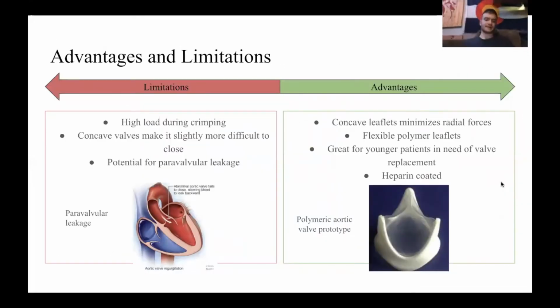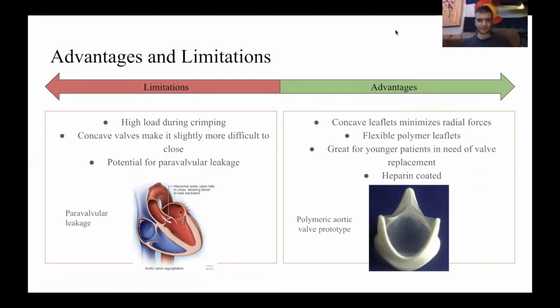So our device has advantages and limitations. To begin with the limitations, there's a high load during crimping. The concave valve shape makes it more difficult to close due to the blood pressure on the valve. And then there's potential for paravalvular leakage due to this. Some advantages are that the concave leaflets minimize radial forces, which is good. There are flexible polymer leaflets which provide the strength that a mechanical valve leaflet would with the compatibility of a bioprosthetic valve. And then they're great for younger patients in need of valve replacements because it's minimally invasive, and the heparin coating allows for no blood clotting to form.